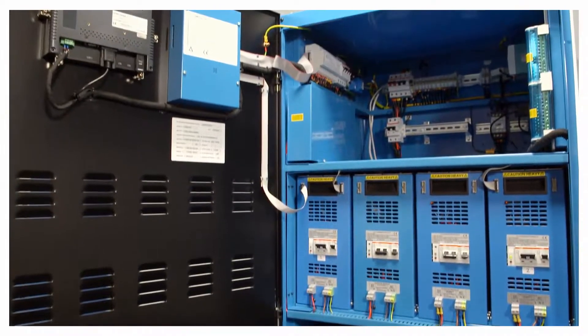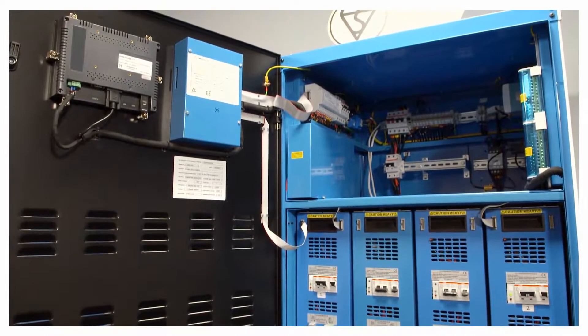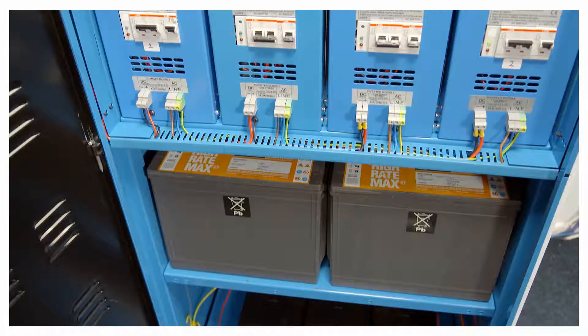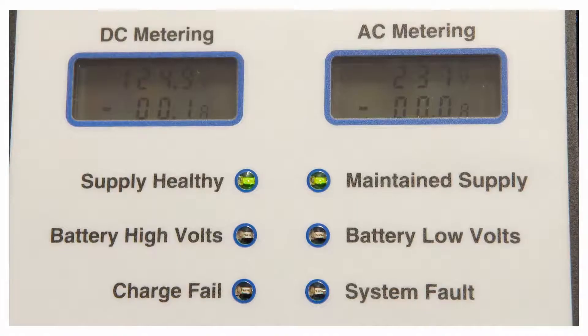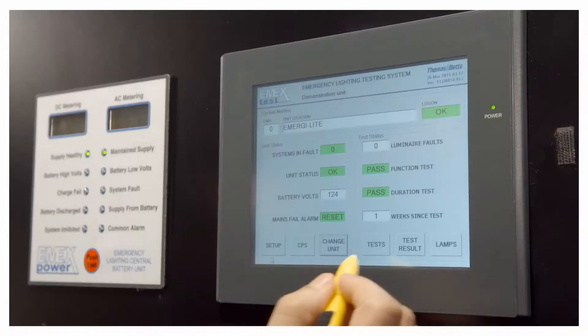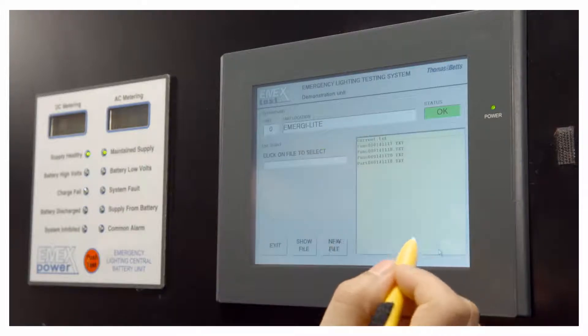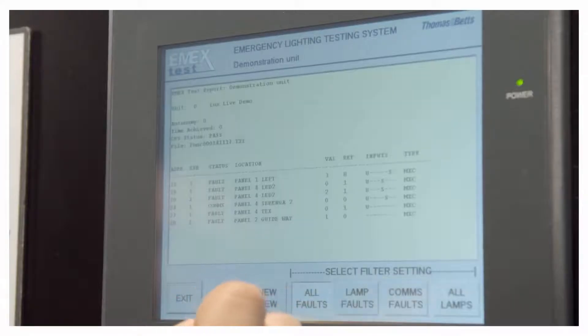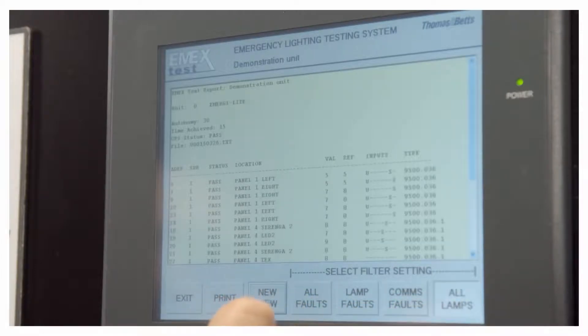Looking inside our EMEX central power system, you can see all the components are housed together. Typically, the lead acid batteries here have a design life of 10 years, but we can use NiCad batteries to increase that to 25 years if required. This particular system comes with an optional touch screen to provide fully automatic testing. Because the maintenance for a central power system is all in one location, this can reduce the running costs, which means in the long run it can be a more cost-effective solution.